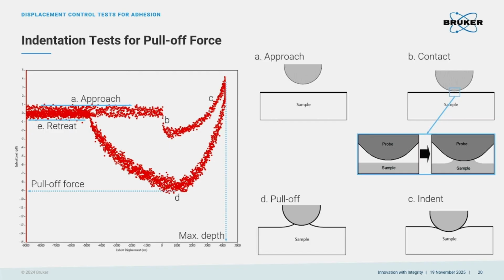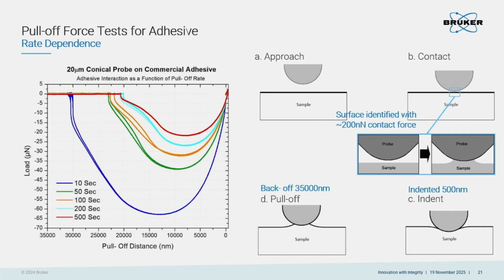And then we increase the force, and the tip will penetrate into the sample deeper and deeper. Then we unload the force. But at the very end of the unloading segment, we typically have a very large force, which we call the pull-off force, the maximum attractive force, and then it goes down to totally out of contact. So this is the entire so-called four stages of a pull-off force test. It has another name, actually, in force testing. Okay?